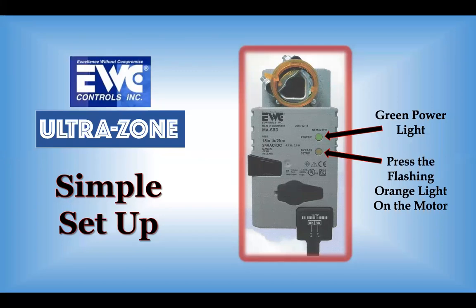Use the screwdriver that comes with the zone panel or the head of a pen or pencil and press that button in. At that time, this goes into its own setup. It closes itself, captures a static, burns that into a chip. Then it opens itself wide open, captures that static, burns it into the chip.